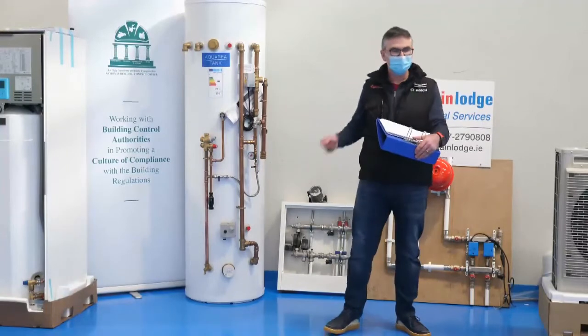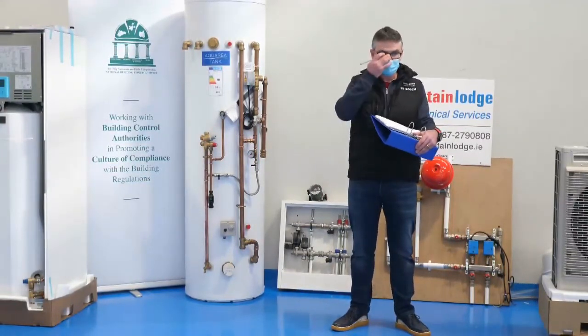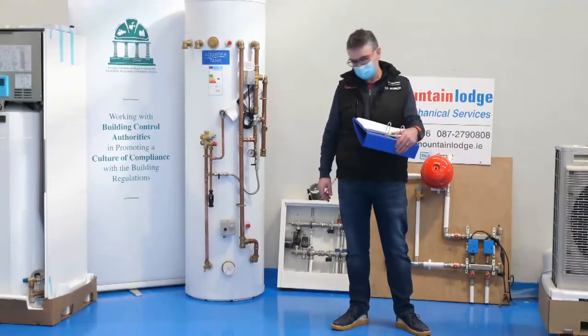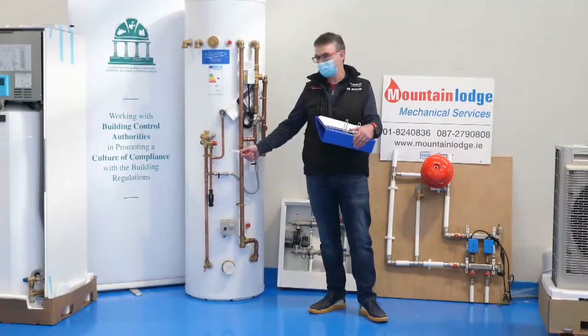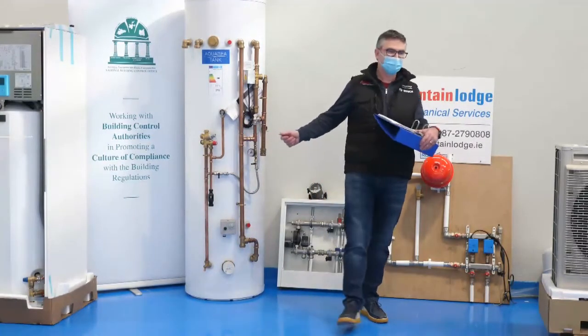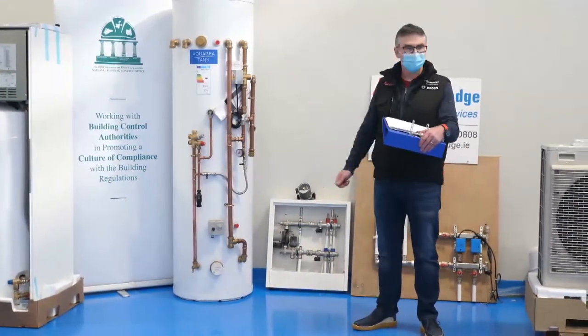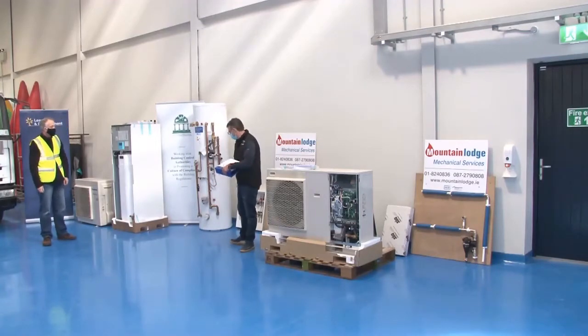If it's at the back of the house and down at low level, at footpath level, maybe even turned down again when it comes out. Because when that water blows off, you don't know how hot it is. It only fails for a reason. If it fails because that water's got too hot, it could be over 90 degrees water coming down. So you want it coming down somewhere where it's gone straight away. So that's just on that.